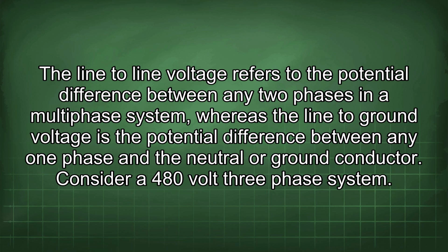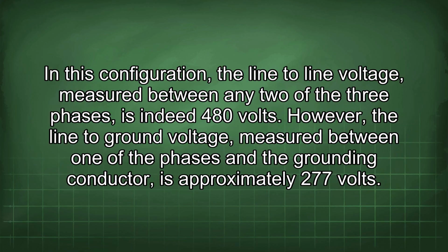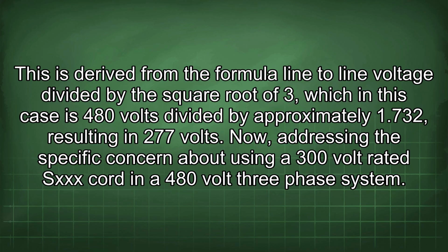Consider a 480-volt three-phase system. In this configuration, the line-to-line voltage measured between any two of the three phases is indeed 480 volts. However, the line-to-ground voltage measured between one of the phases and the grounding conductor is approximately 277 volts. This is derived from the formula line-to-line voltage divided by the square root of 3, which in this case is 480 volts divided by approximately 1.732, resulting in 277 volts.